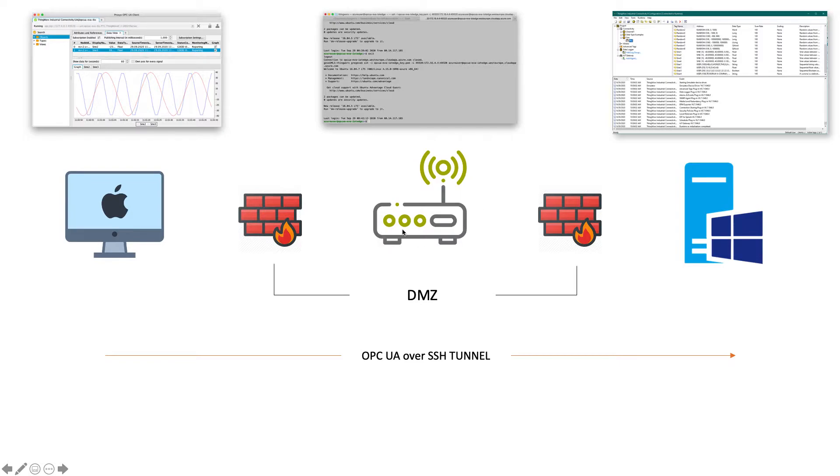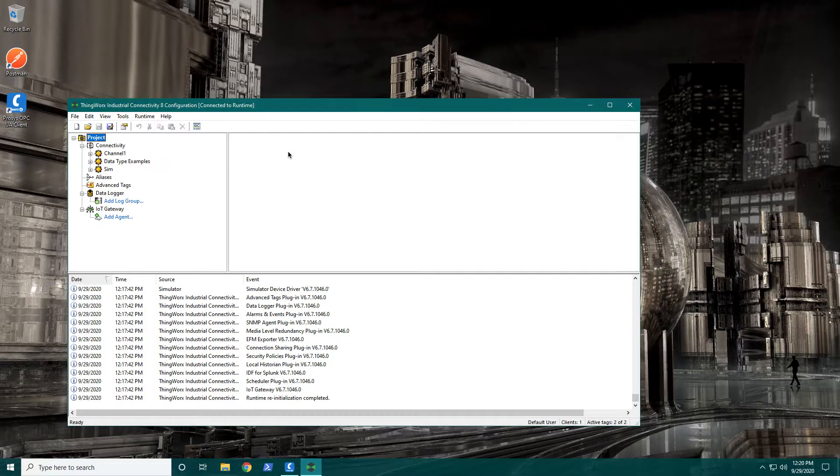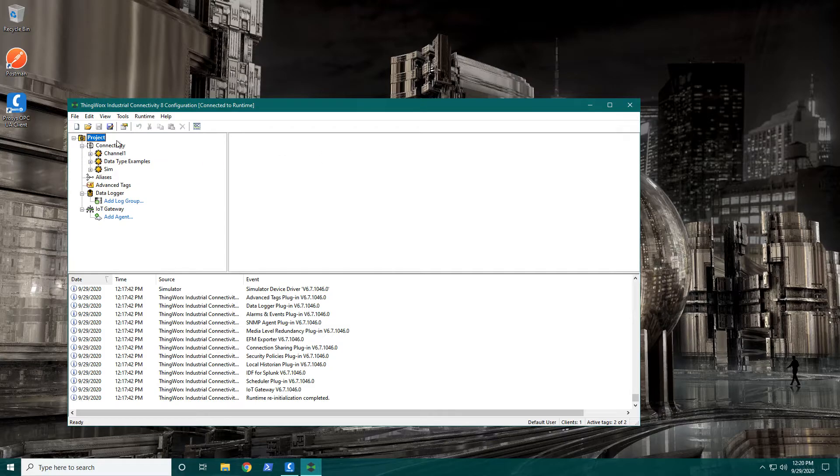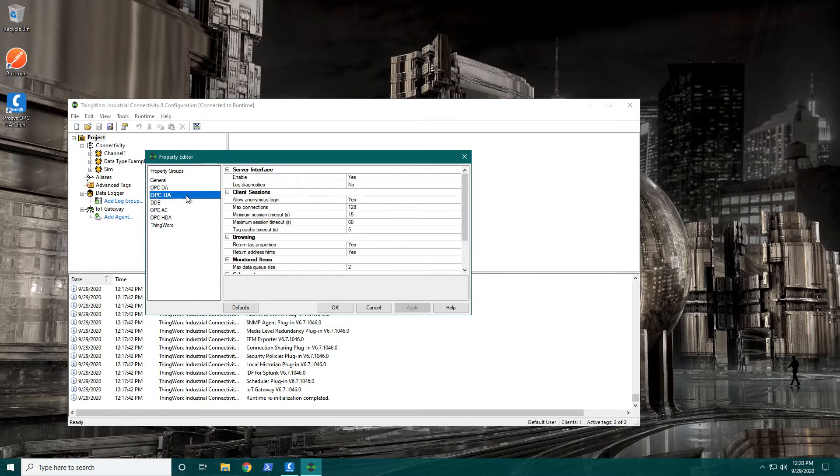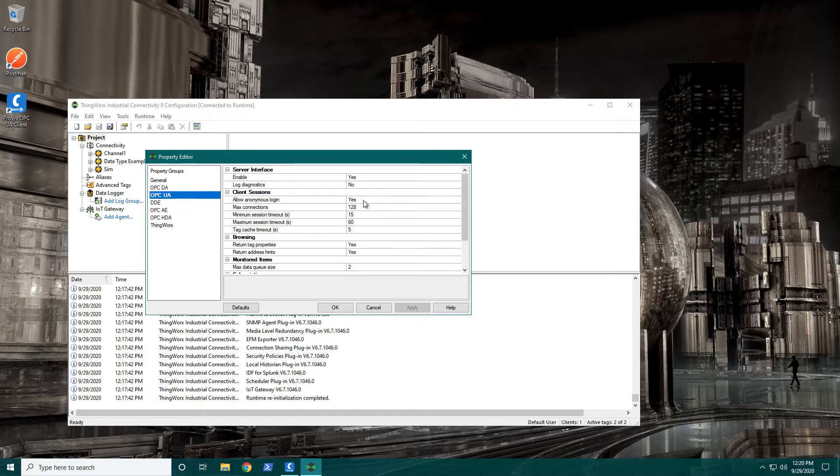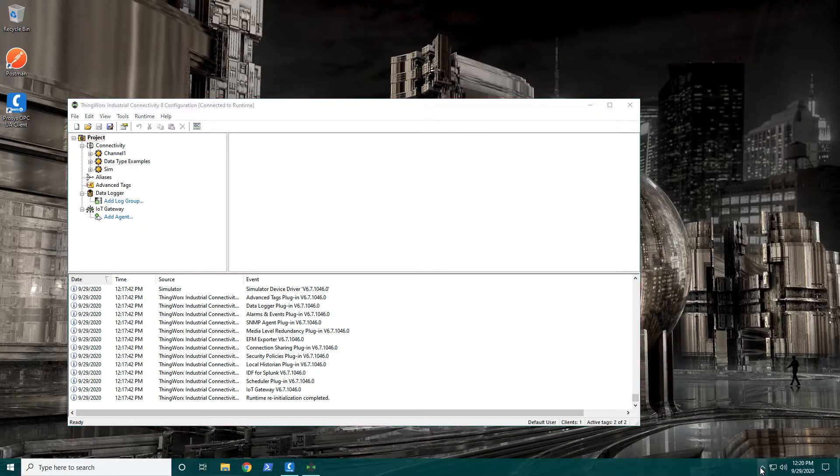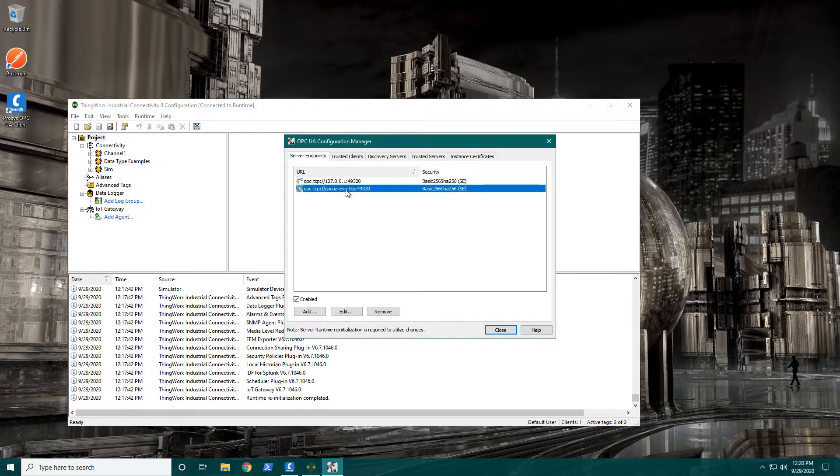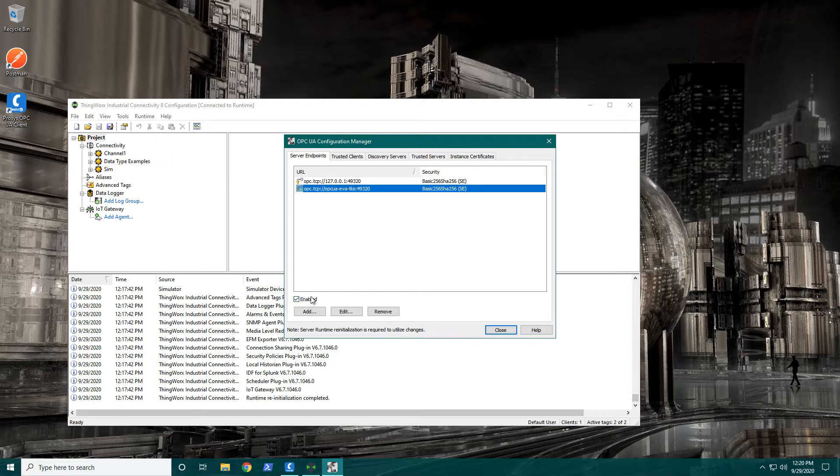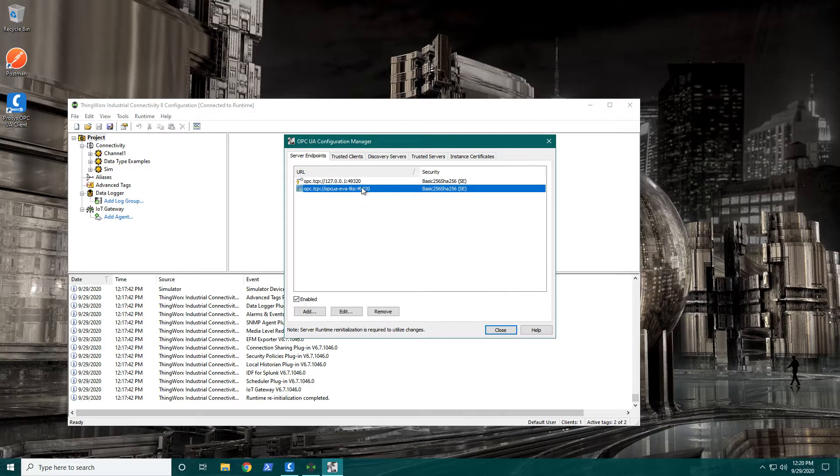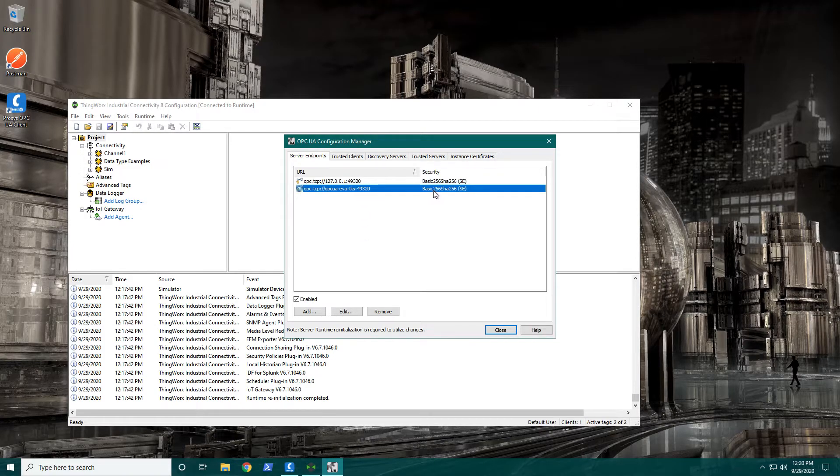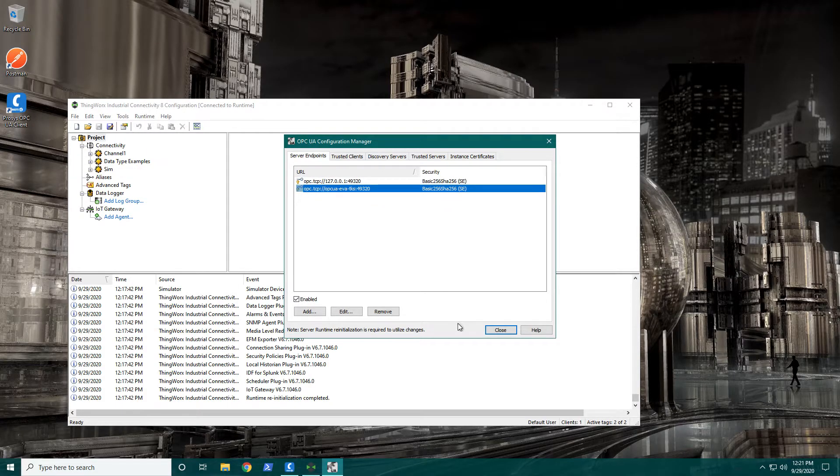Let's have a look at it. Connected via remote desktop to the Windows machine that's running Kepware. I will just mention briefly that I have configured OPC UA to use allow anonymous access because I don't have a particular OPC UA user setup. If we have a look at the OPC UA configuration, you can see here that I have enabled the remote endpoint for the binding so that this is accessible from another machine, not just this one. We're using Basic 256 SHA 256 for signing and encrypting the communications.